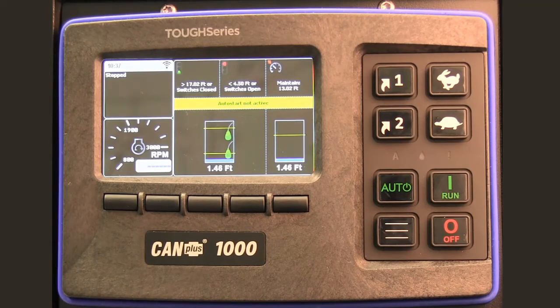The dashboard is showing that the start event is when the level is above 17 feet or both switches are closed or floating. The stop event occurs when the level is below 4.5 feet or both switches are open or down. Finally, the maintain point is at 13 feet.